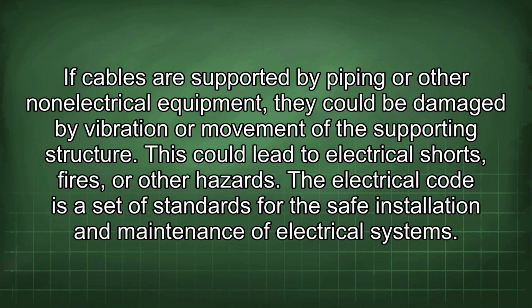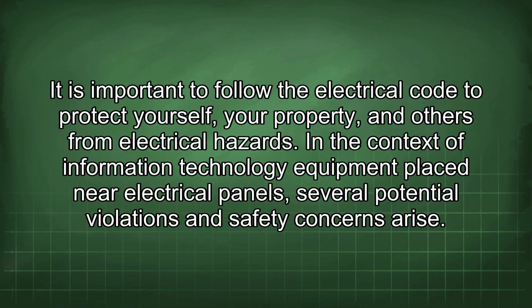If cables are supported by piping or other non-electrical equipment, they could be damaged by vibration or movement of the supporting structure. This could lead to electrical shorts, fires, or other hazards. The electrical code is a set of standards for the safe installation and maintenance of electrical systems. It is important to follow the electrical code to protect yourself, your property, and others from electrical hazards. In the context of information technology equipment placed near electrical panels, several potential violations and safety concerns arise.